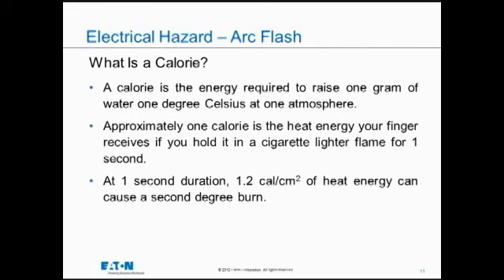So the unit of energy that was chosen to describe the arc flash hazard is a calorie, and we put calories over a square centimeter of surface area to get our limit. And the top line is talking about the definition of a calorie. If you were in the science lab and you wanted to figure out how much energy it takes to raise 1 gram of water 1 degree C, it would be 1 calorie. If you were doing a movie, let's say on YouTube, and you wanted to be funny about it, you could hold your finger over a lighter for 1 second and say, yeah, I got 1 calorie of energy coming at me. But at the bottom, the known limit of human skin is 1.2 calories per centimeter squared for an exposure time of 1 second. That's enough energy to get a second-degree burn on human skin. So that's a known limit.